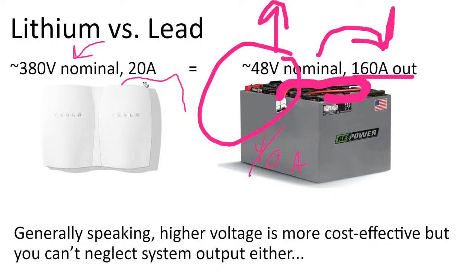So we went out to this project and the battery had these little tiny wires off of it. It's like, oh, that's for a high voltage battery bank. We have a low voltage battery inverter, it's not going to work. He says, no, that's a 48-volt battery. And it's like, okay, well if you decrease the voltage, you increase the amperage. So if you have a low voltage battery, you've got to have big giant battery cables coming out of it if you're powering a heavy load. And we were putting on a 12 kilowatt inverter for the whole house.